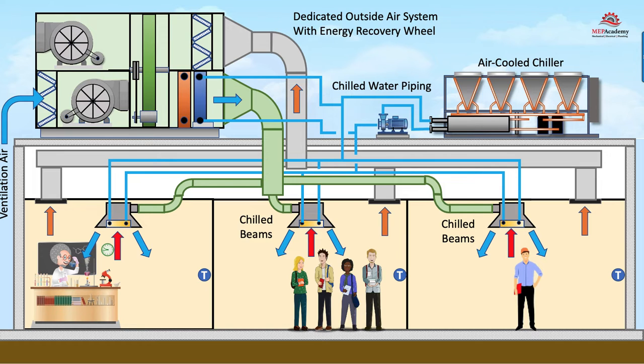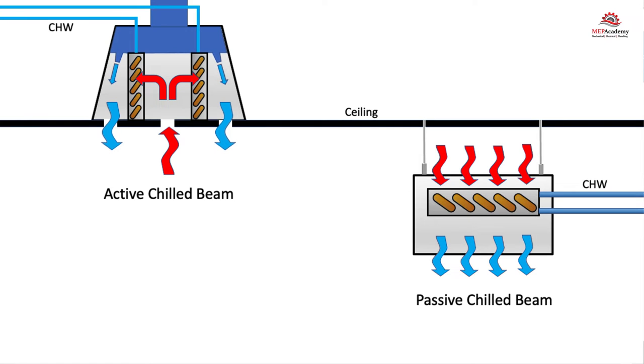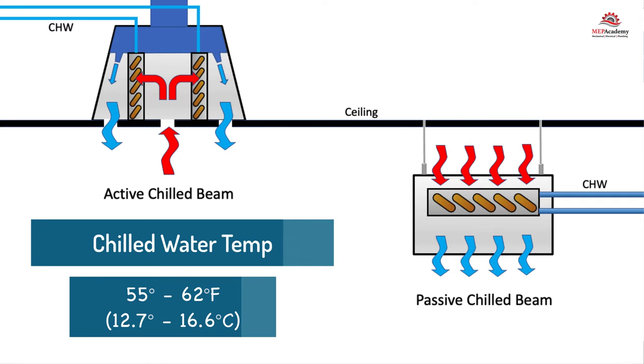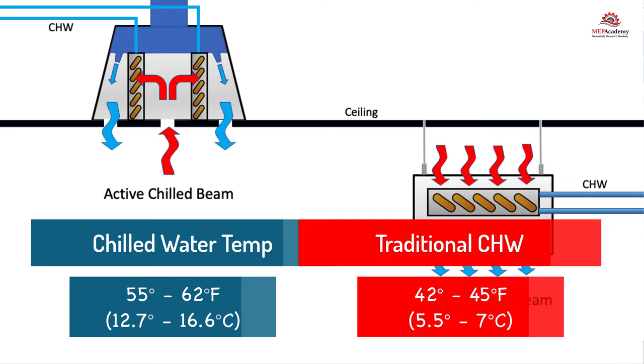If the level of humidity is not properly managed by the AHU, then condensation can occur on the chilled beams and water could drip on the space below. The chilled water temperature to a chilled beam is in the range of 55 to 62 degrees Fahrenheit (12.7 to 16.6 degrees Celsius), which is higher than a traditional chilled water system of 42 to 45 degrees Fahrenheit (5.5 to 7 degrees Celsius), in order to avoid condensation.